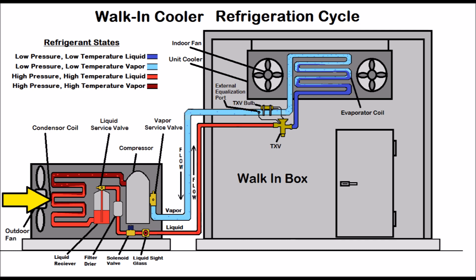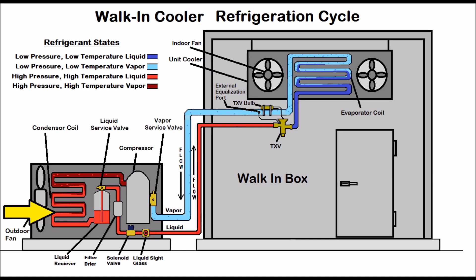There is no temperature change once it hits the saturated state. It continues to reject heat until it turns into a complete liquid. Then the liquid refrigerant lowers in temperature as it rejects heat and turns into a sub-cooled liquid. Sub-cooling is the temperature decrease in liquid form — specifically the temperature difference between where it comes out of the saturated state as a complete liquid and where it enters the liquid receiver.